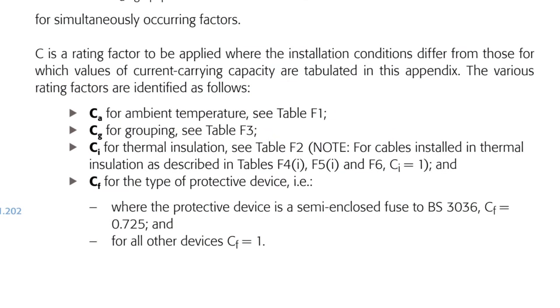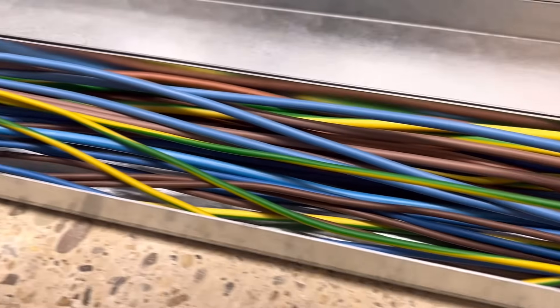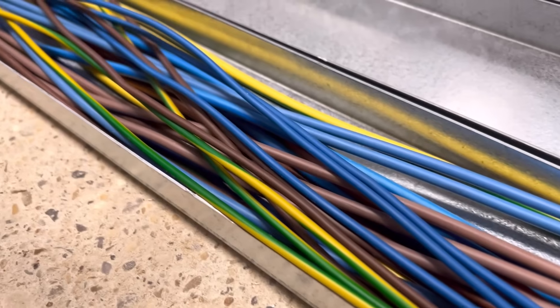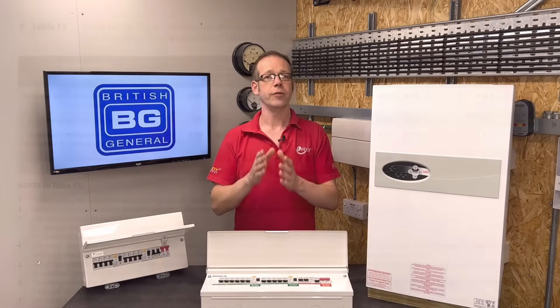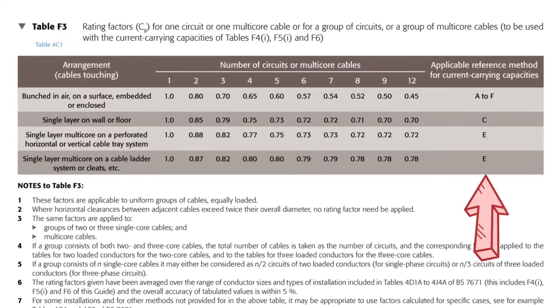CG is the rating factor for grouping. Grouping is when two or more cables are run together, and we need to take it into consideration because of the heat dissipation issue — cables in proximity make it harder for each to dissipate heat, as each is affected by the heat from its neighbour. We get the information from table F3 of the on-site guide. Down the left-hand side are four potential installation methods: bunched together in any way (on a surface, buried in a wall, or in trunking); in a single layer on the wall or floor; in a single layer on tray; and on cable ladder or similar. Across the top is the number of circuits grouped together from 1 to 12. The final column shows reference methods for the way cables are installed.